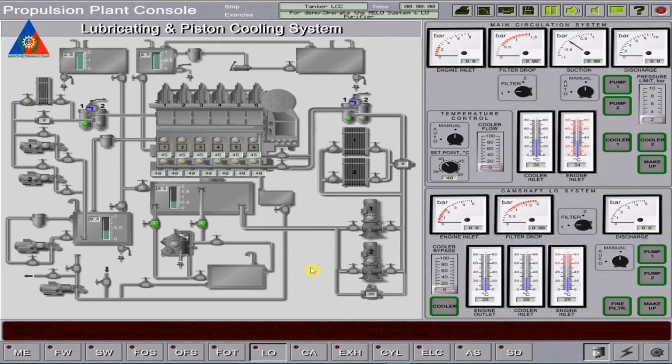In the camshaft lubrication system, lube oil of certain temperature is supplied under certain pressure for circulation and lubrication points, including the camshaft bearings and valve tappet guides. Lube oil is collected in the camshaft crankcase oil pan, where it is maintained at a level sufficient for being caught by the rotating cams for the purpose of lubricating the cam working face.